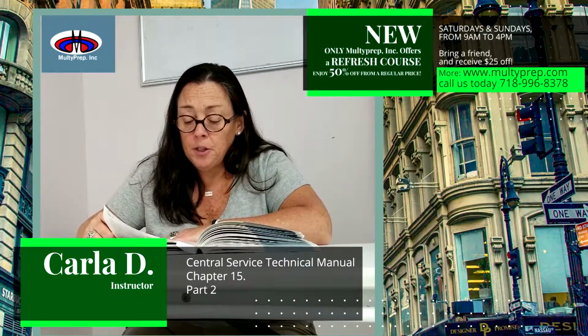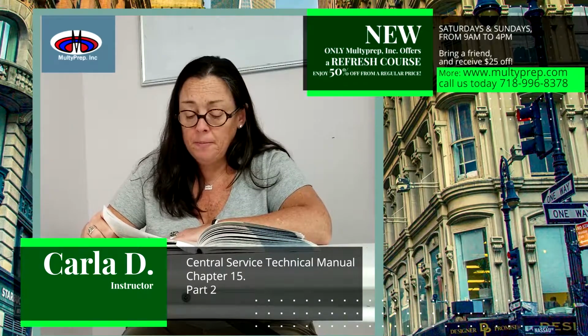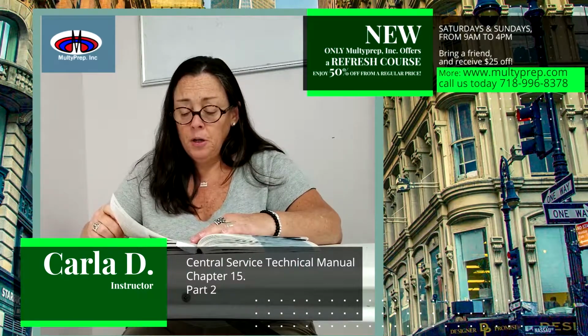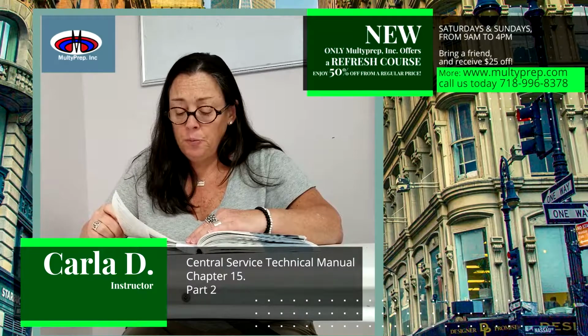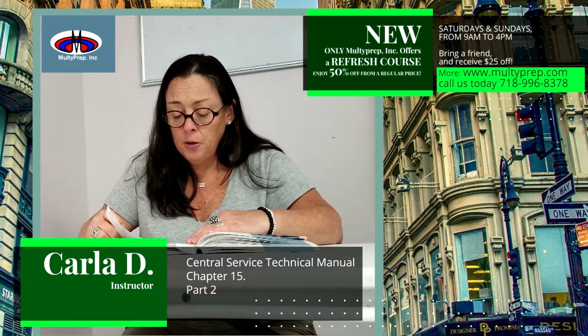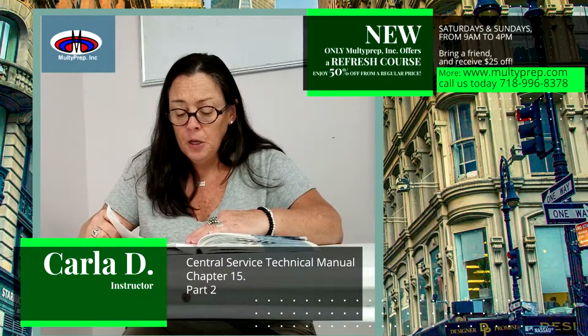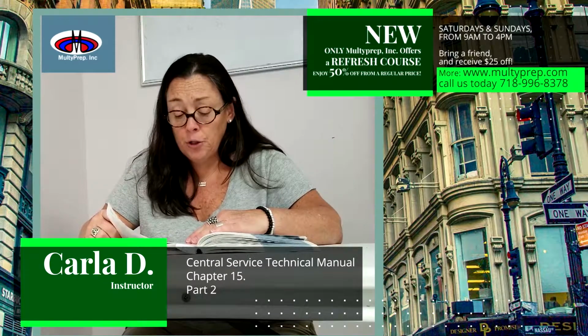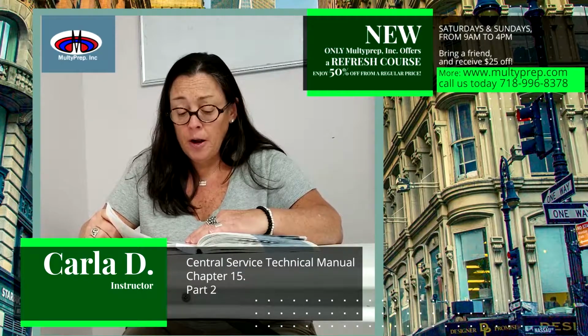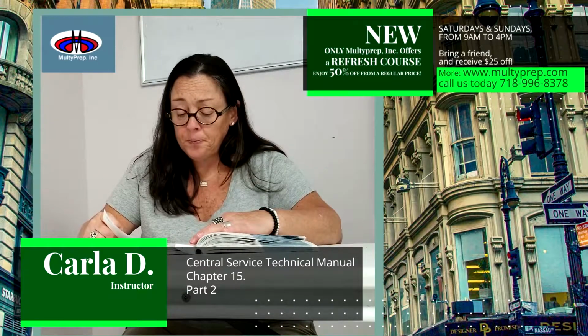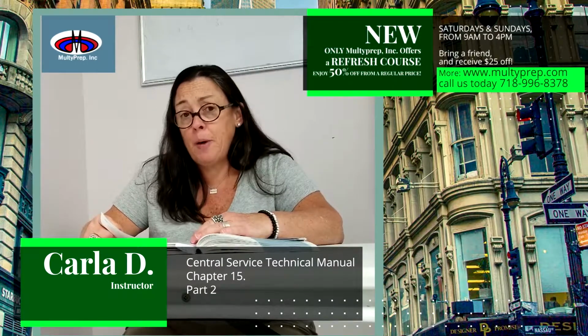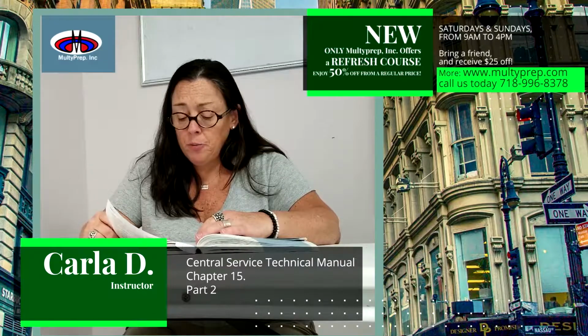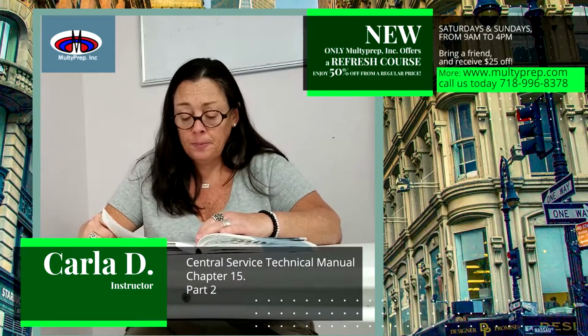Packaging. Packaging materials can affect the penetration of hydrogen peroxide. Packaging materials used in sterilizers should be designed to optimize diffusion of the hydrogen peroxide and not interfere with the RF energy, radio frequency energy, or absorb hydrogen peroxide. Trays and container systems from the sterilizer manufacturer and Tyvek pouches are compatible. Check with tray and sterilizer manufacturers before purchase and use of containers.